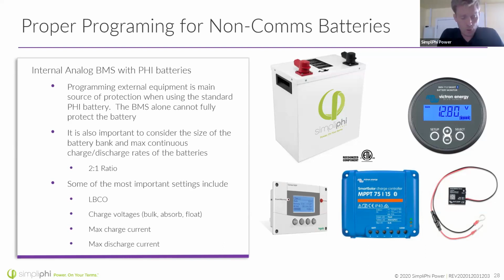That's a great question. And so for LFP, as long as you use our 56 volt recommended absorb, there's essentially no difference. The number of cycle lives doesn't get influenced by that 56 volts very much like it does with NMC batteries. So Tesla, for instance, has 2 types of battery cells. They offer NMC cells, especially on their longer range vehicles, because they're a little bit lighter. And they also offer LFP batteries. And one way to know what kind of Tesla you have is if it tells you not to charge your car above 90%, unless you're going on a long trip, then you have an NMC battery pack in your Tesla. NMC is much more influenced by that high voltage side of the charge cycle than LFP is.